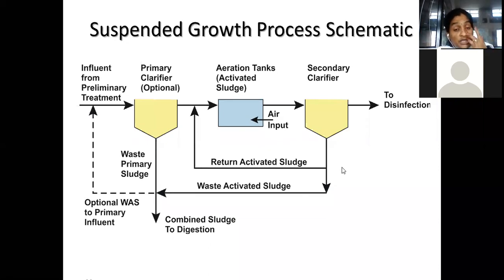During this time, the maximum amount of organic impurities present in sewage will be consumed by the microorganisms, and once consumed, they become heavier. After that particular design period, we can send that sewage towards the secondary clarifier. In the secondary clarifier we allow them to settle at the bottom. What happens in a clarification process? Clarifiers are provided to separate the solid and liquid parts, because we are reducing the velocity of flow and making settleable particles settle down.